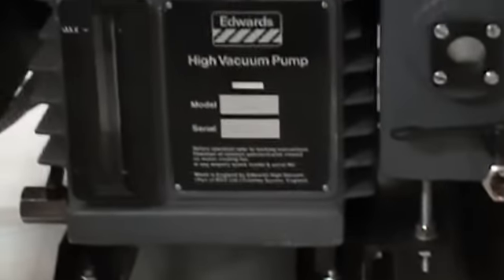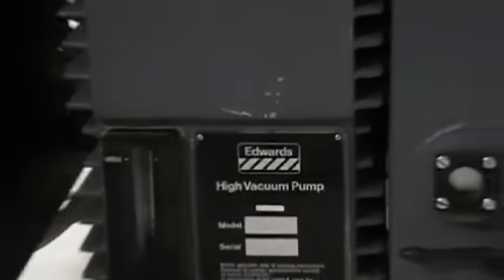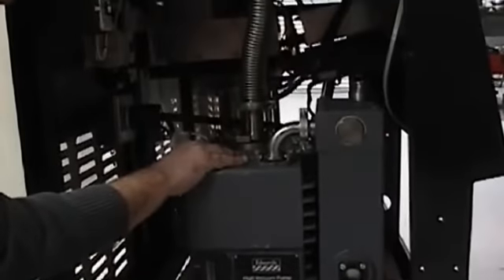We have raised the pump so it clears the caster height and put this on a maintenance cart. So you have a custom built maintenance cart here with locks. To service this pump, you would simply twist lock, unplug, disconnect this connection here, which is your intake connection, and wheel out for draining oil, servicing, whatever you need to do. Everything that was done was with maintenance in mind.